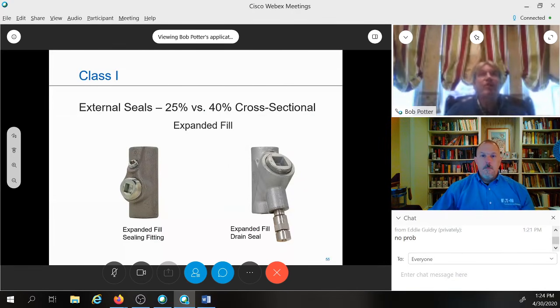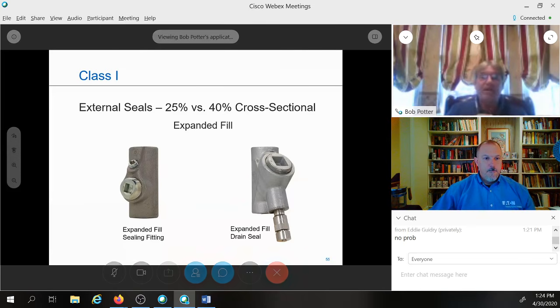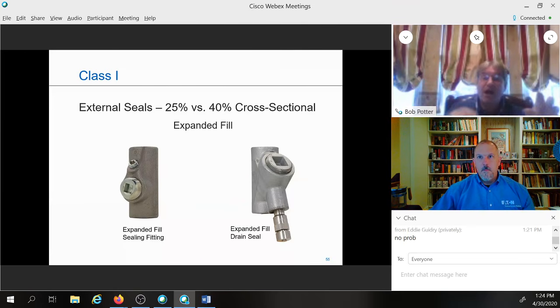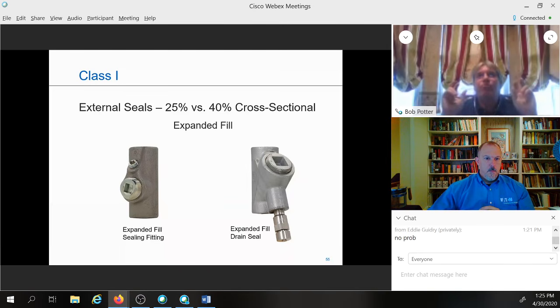If you're installing it in conduit, which I do see applications where people install the cable within a conduit, when you just read the code at face value, it tells you that you need to remove the jacket and separate those conductors. But obviously, that's not always practical, especially with things such as variable frequency drive cable that gets a little sensitive if you start playing with its insulation. So what the National Electrical Code does allow is, if I can have an approved sealing method within the enclosure, and that's all it says, approved sealing method.